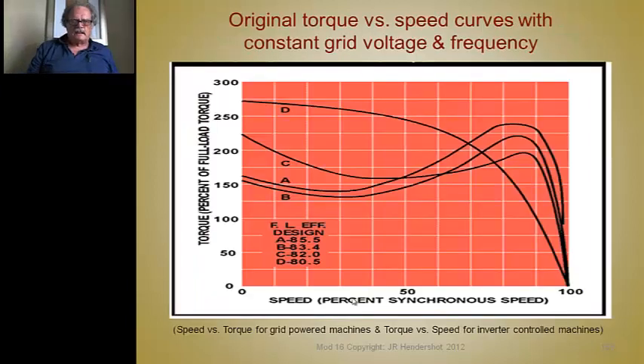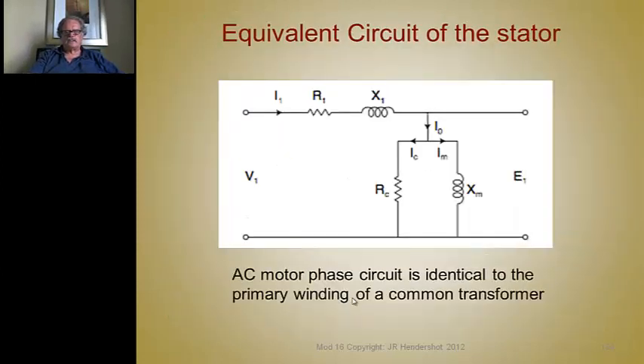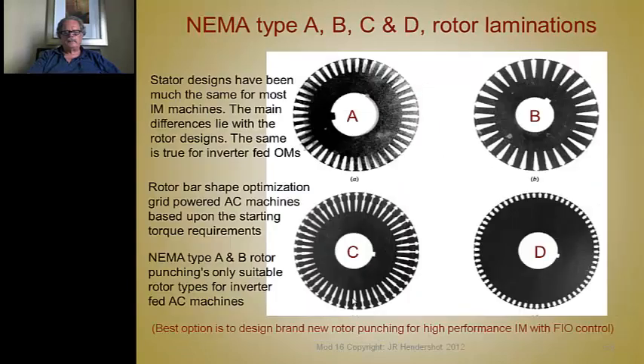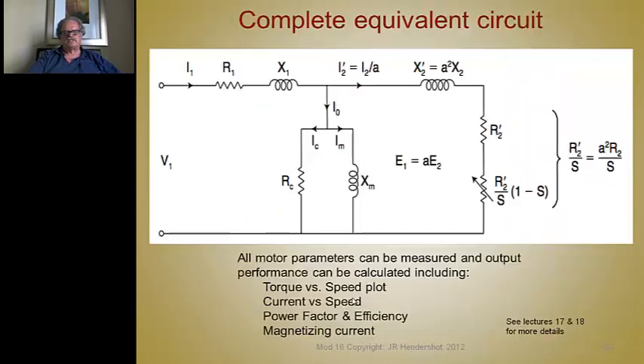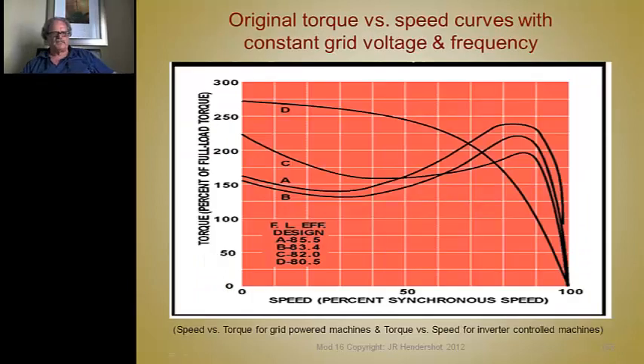This is a set of torque speed curves that really should have been close to this picture here: A, B, C, and D. Think of those laminations. Those laminations go with these different torque speed curves. Now I've changed this and put it in terms of torque speed instead of speed torque. But those are your A, B, C, D curves. You see D, the one weird one there, has the highest starting torque but very high slip. Now, this one, C, has a stepped bar. It's got two sections of the bar. It's got a small bar close to the OD of the slot and a deep bar below the slot.